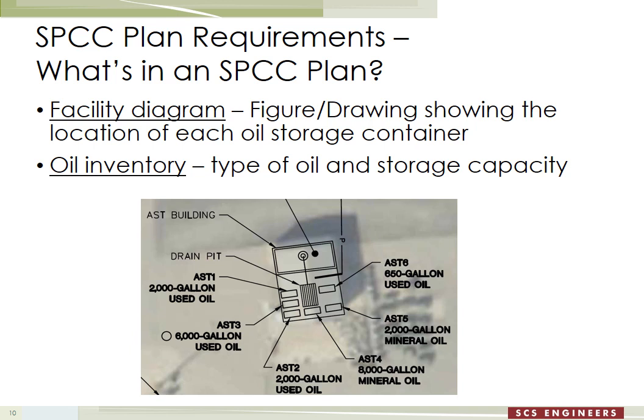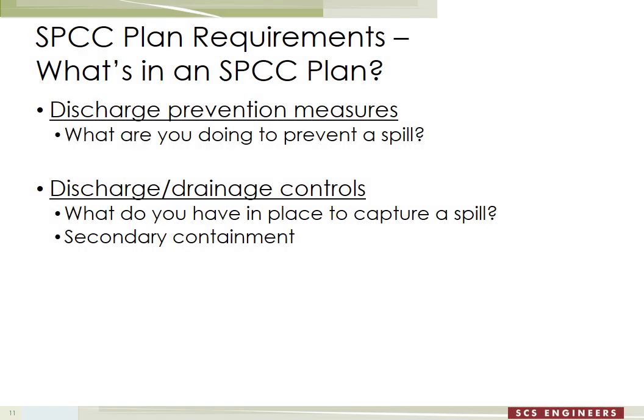The rule says you have to write an SPCC plan. The plan must have a facility diagram — a figure or drawing showing the location of each oil storage container, with a unique name, capacity, and type of oil shown. The plan needs to have an oil inventory including the type of oil and the storage capacity, most commonly presented as a table. SPCC plans need to include your discharge prevention measures — what policies and procedures you have in place to minimize your chances of having a spill in the first place.